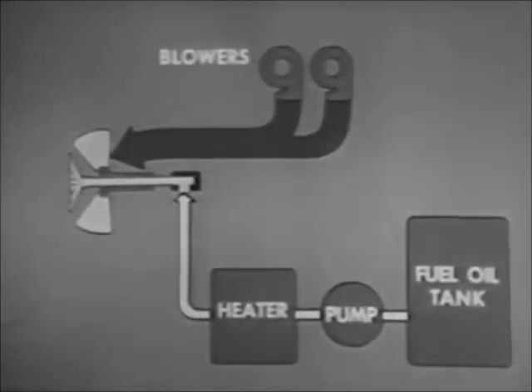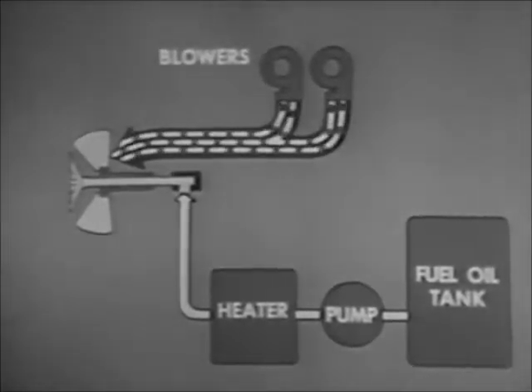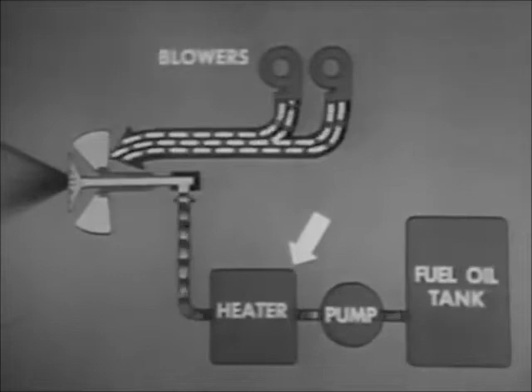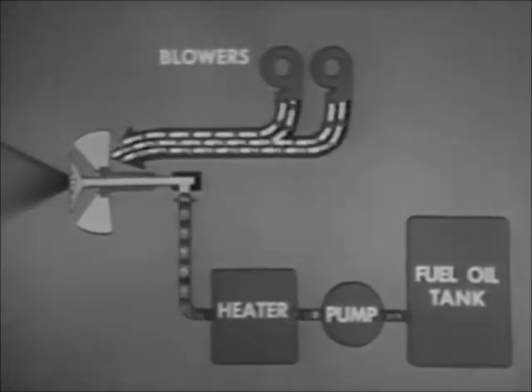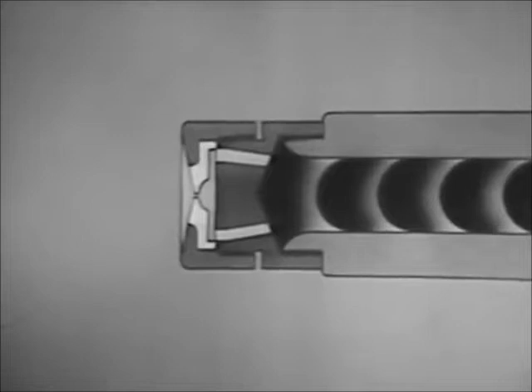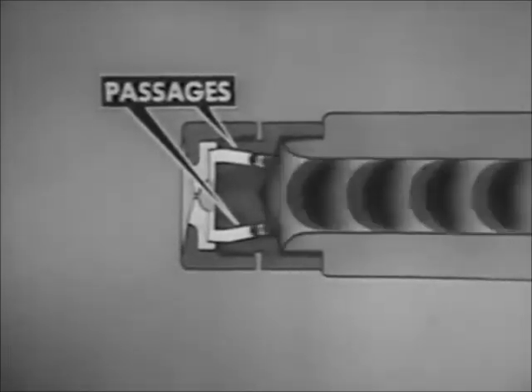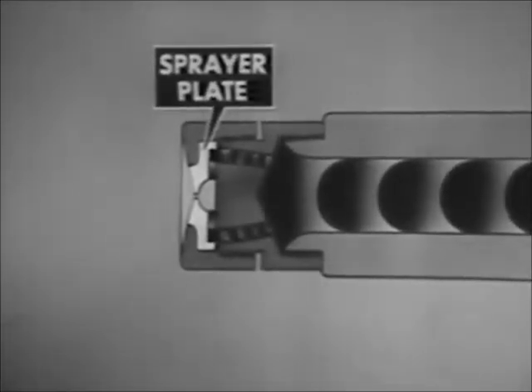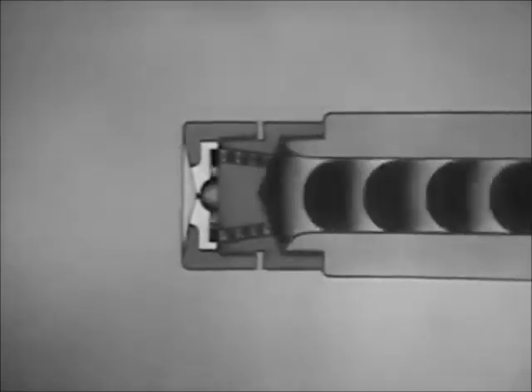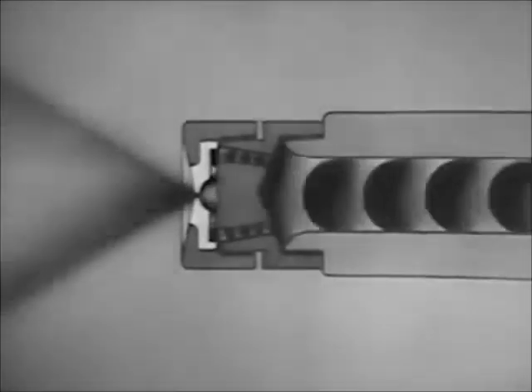The forced draft blowers send a strong blast of air to the burner. The fuel oil pump sends the oil through the heater where the oil is heated to give it good flow quality, then the oil is pumped to the burner. This simplified cutaway of the burner shows how the fuel oil is forced through the burner barrel to the atomizer nozzle, where a series of passages guide the oil to the sprayer plate. The sprayer plate makes the oil rotate at high speed, breaking it up into particles, and the oil leaves the atomizer as a hollow mist-like cone or spray.